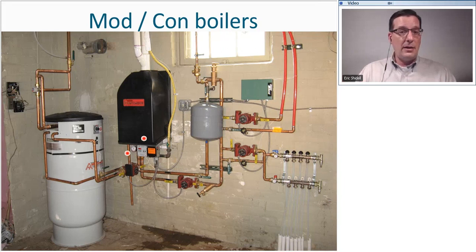Another feature of ModCon boilers is that they use a PVC flue, and most of them are direct vent, meaning they have a dedicated combustion air intake coming from the outdoors to feed the burner and a dedicated exhaust going back to the outdoors. And you can see the PVC flue and intake assembly here on this boiler. ModCon boiler systems can become very complicated. This one is relatively simple, but you can see that there is a whole lot of stuff going on here. As we move through the rest of our course, we will discuss in great detail what all of this stuff is. Because when it comes to identifying which way the water goes in one of these boilers, that can be a challenge. You're going to be looking for the pipe connections to see supply and return. And looking at the circulator pumps is usually the best way to go, because in a system like this, water is going in all kinds of different directions.